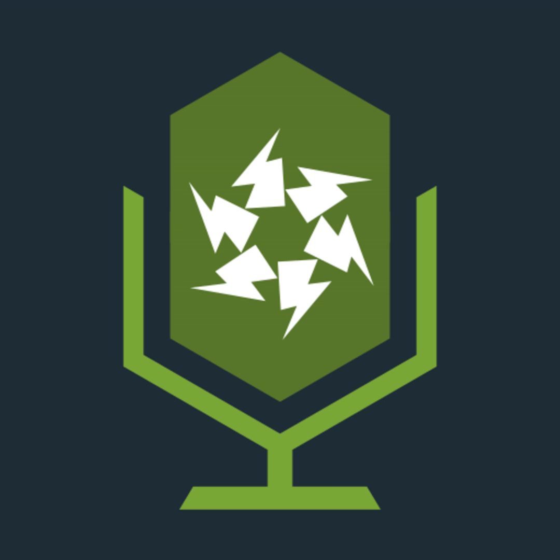With regards to earth electrode testing, it's always a good idea, if you're going to do an earth electrode resistance test when you install it, let's say now, this time of year, we're in a fairly dry spell. It's summertime, but if you were to install an electrode, you'd want to test it again in the polar opposite of the weather conditions, really. So dry, wet, frozen conditions.